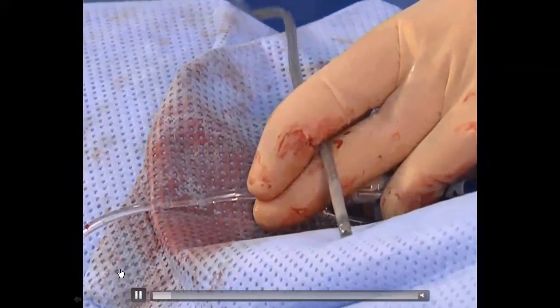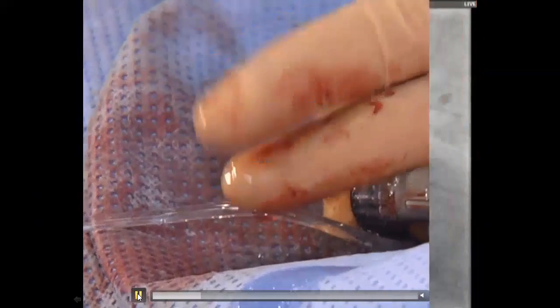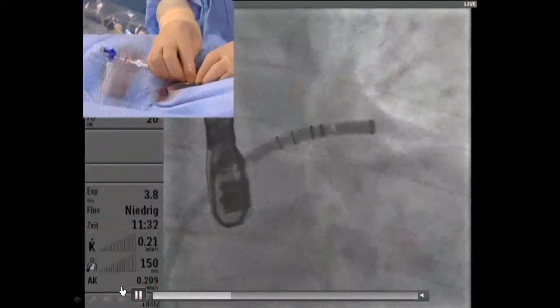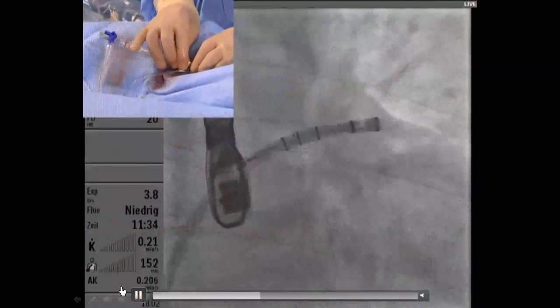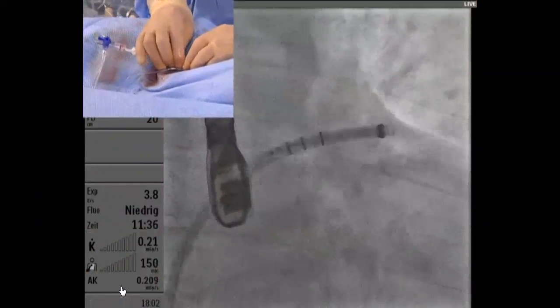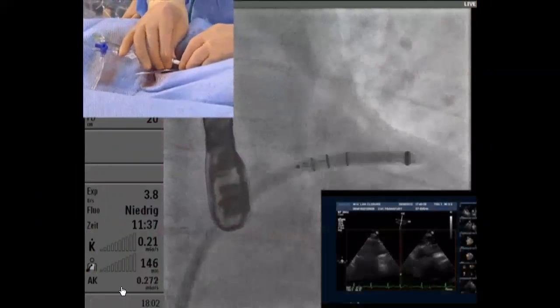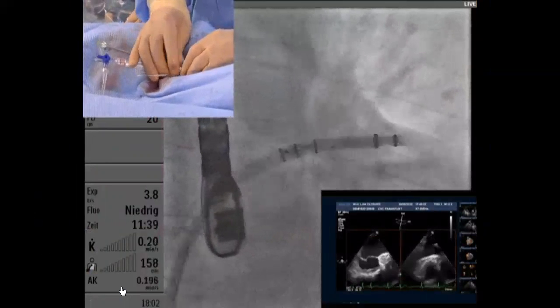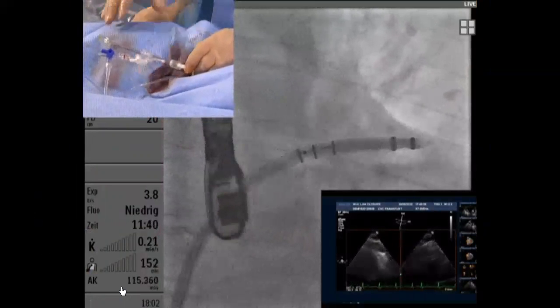And this is the actual delivery catheter. So the delivery catheter, which has the Watchman in it, goes into the delivery sheath. The delivery sheath is the one with those three markers. And the delivery catheter goes with the Watchman inside into the delivery sheath.